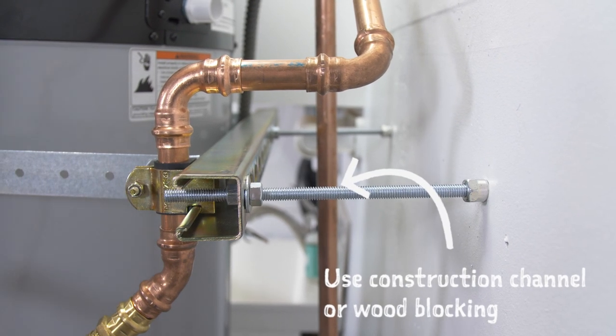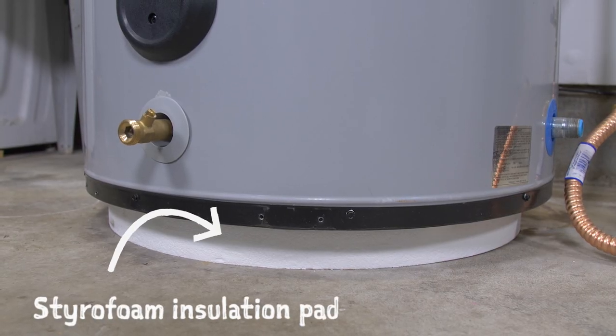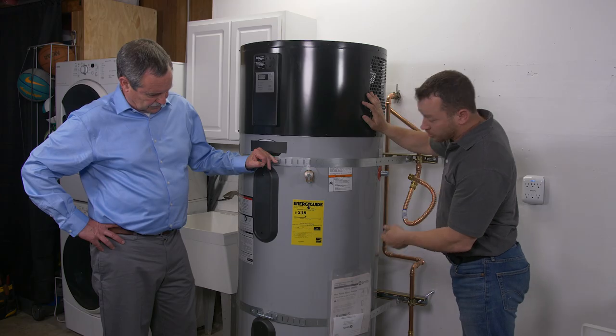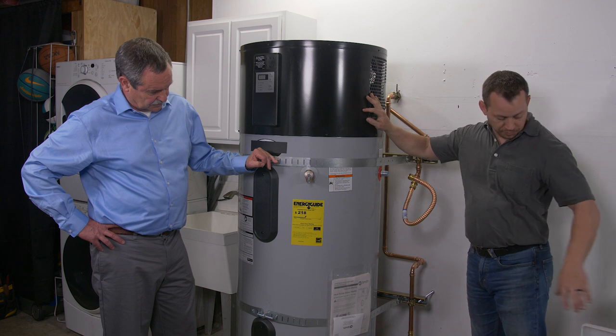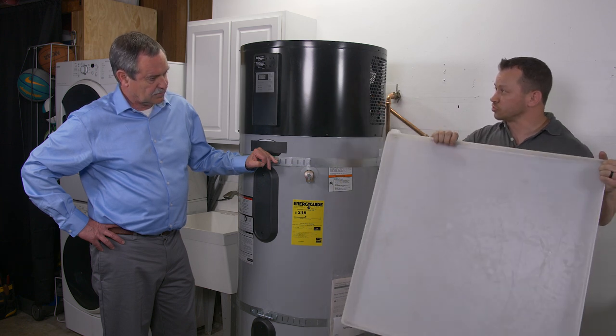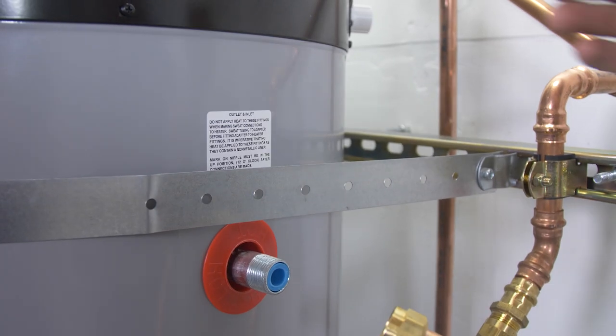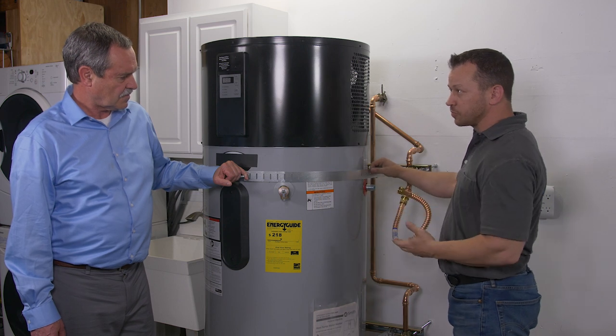We've got a styrofoam pad on the bottom to prevent the concrete from absorbing the heat from the water heater. Of course, if we were on a wood frame structure or something like that, we'd use a drain pan. We've also got seismic strapping on here. It's required here in the Pacific Northwest.